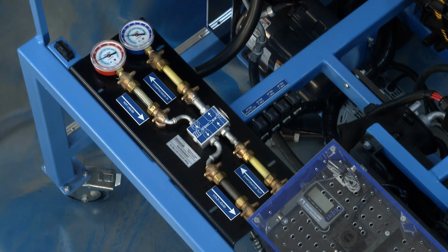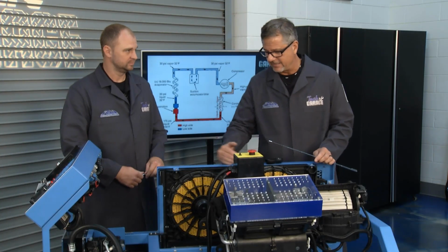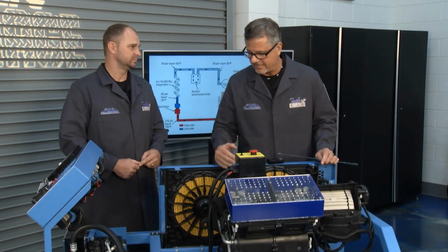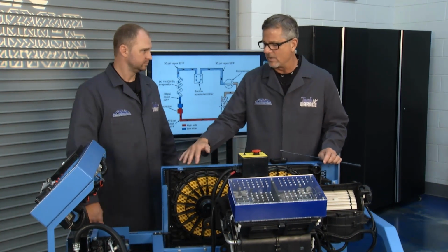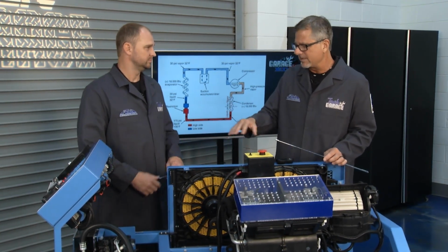Now you should be able to feel those lines. You should feel a difference, right? Right, so if your compressor's working like it should, you should have a hot line coming out. And in our case, we do. High pressure gas equals hot gas. Awesome, so it got it nice and hot, ran it over to the condenser, went in here hot, changed state. So we're going to have a little temperature change here from going in to going out. Not too much, maybe 20 or so degrees.